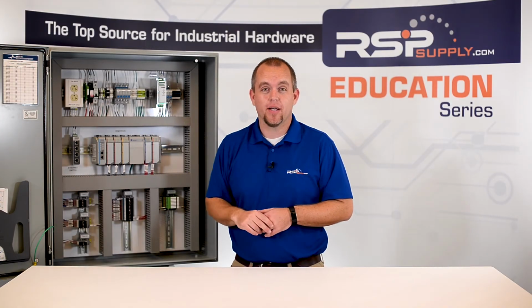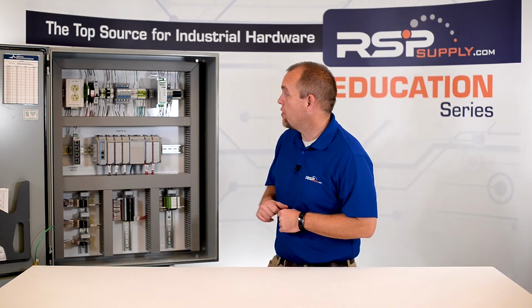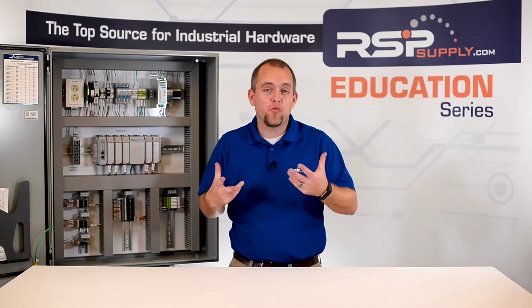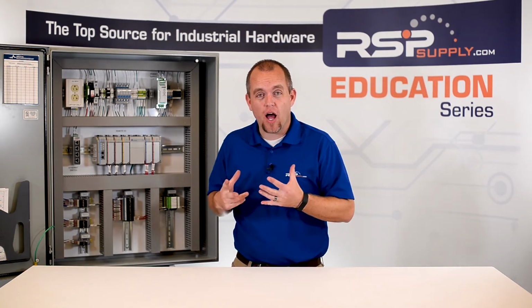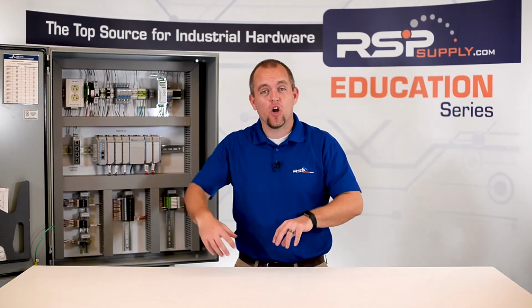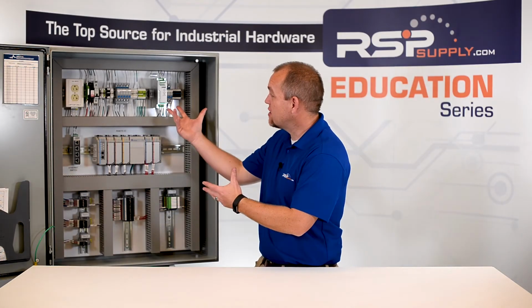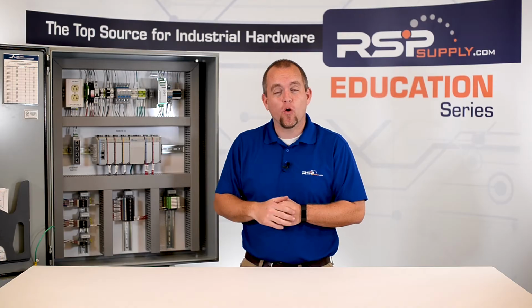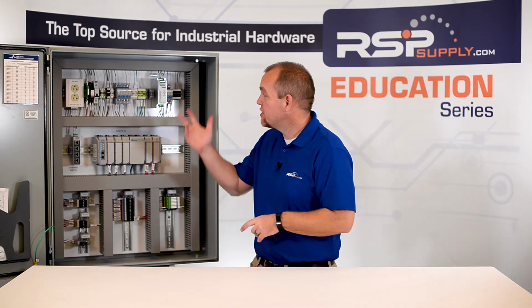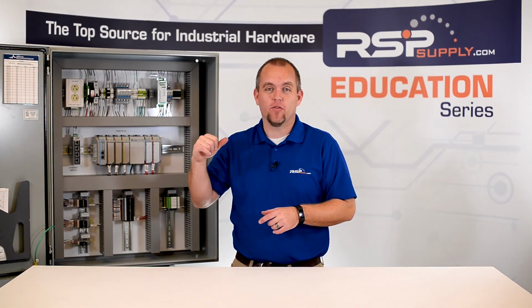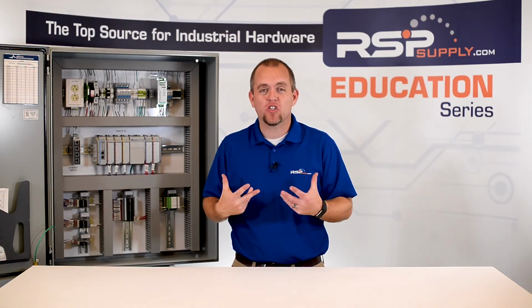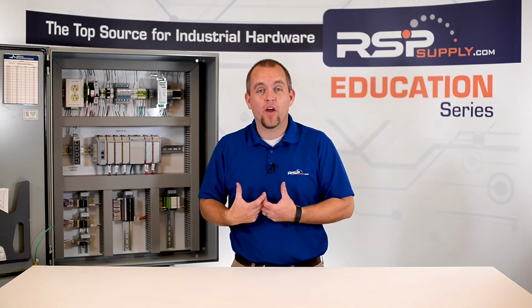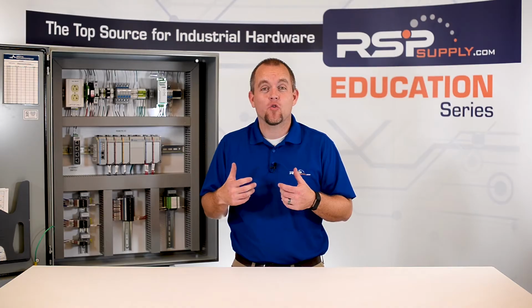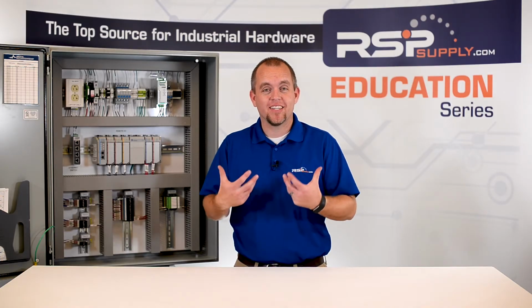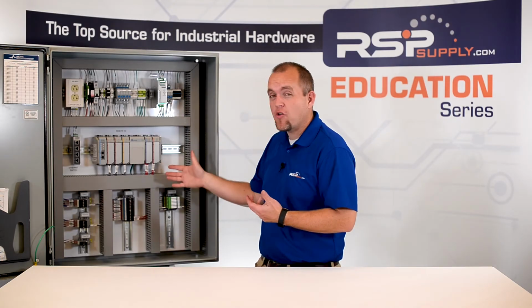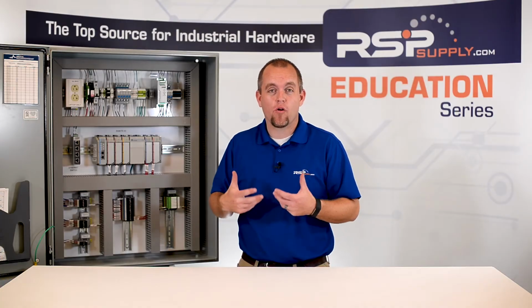We also want to make sure that the enclosure and the door enclosure are properly grounded and tied to the main grounding bus. Next, let's talk about a power supply or a UPS. A power supply is going to convert one type of power to another type of power. In the case of the panel we have here today, we're converting 120 AC voltage to 24 volts DC voltage. It is common to see a power supply used in conjunction with a UPS, or an uninterruptible power supply. This allows us to continue to power the panel in case of a power failure.